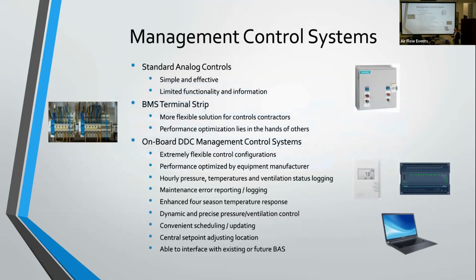Let's talk controls for a minute. Controls are one of the biggest ways you can improve the efficiency of your units. Your standard analog control setups are very simple and effective, but they're limited in functionality and information. More commonly, we're seeing a lot of building management BMS terminal strip units, where the controls contractor wants to take control over the unit, whether they've got an automation system they're going to tie it to, or they're going to install their own controller. The nice thing about that is it gives those control contractors a lot of flexibility to set the units up. However, you're also putting that performance optimization in the hands of someone else rather than the equipment manufacturer, who might know a little more about the proper operation of those units.